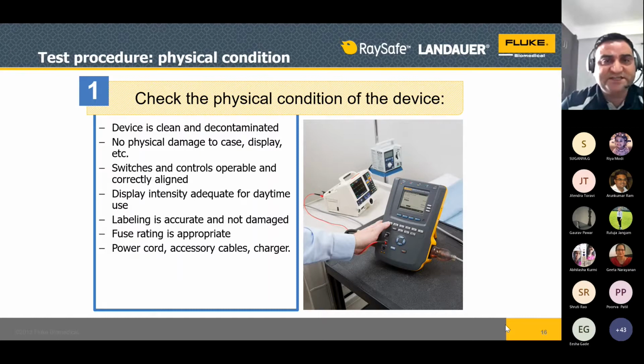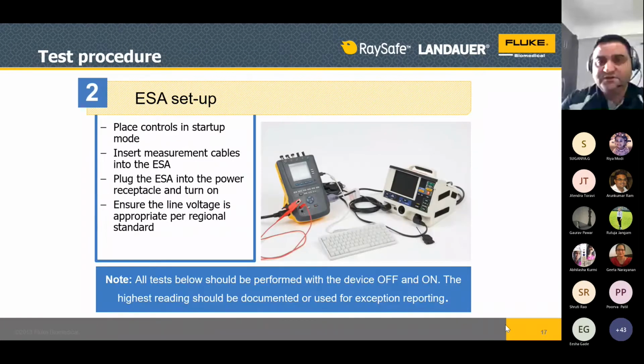So before you do the test, you have to ensure there is no physical damage, the display etc. is okay, and switches and controls are operable and correctly aligned. So you need to check all those things before you start a test. Then you can do a setup. Once you do a setup, you have to ensure always that the red color probe which you are seeing on the ESA, you zero the resistance of the leads. Because if you are not zeroing the lead, whatever measurements you take from the DUT will add on to that particular measurement, and there may be a slight increase in the output value. But once you zero it from the ESA, then you take the actual measurement and that will show you the perfect value.